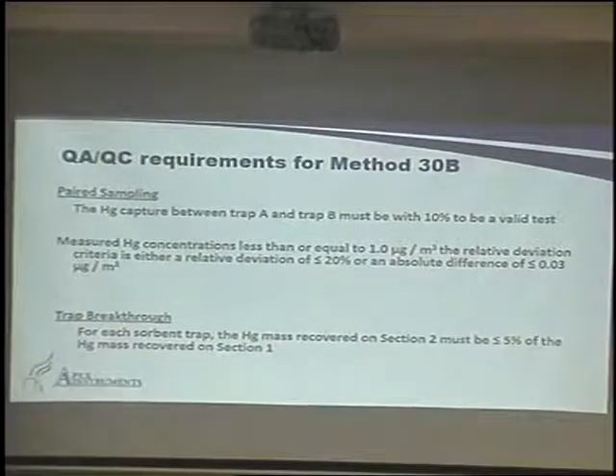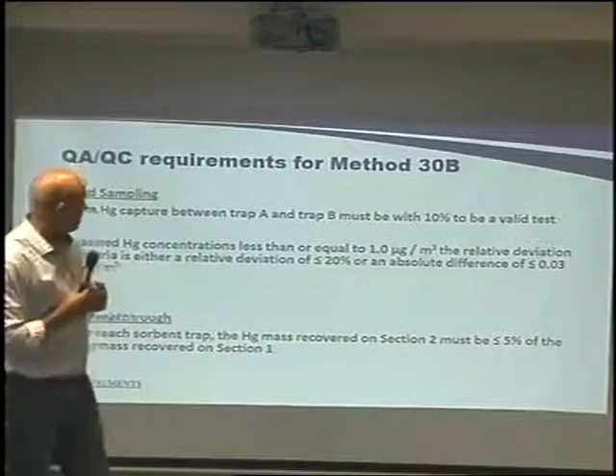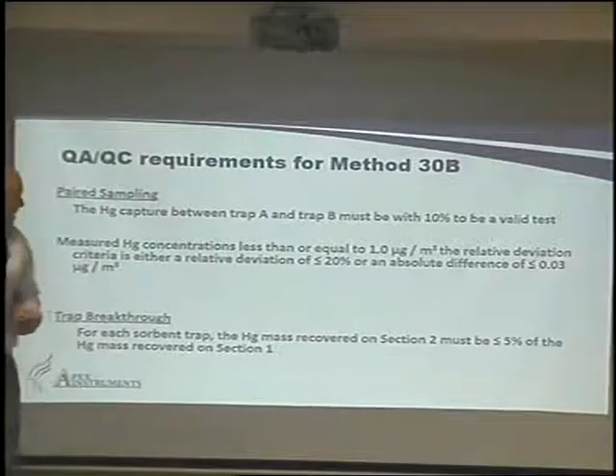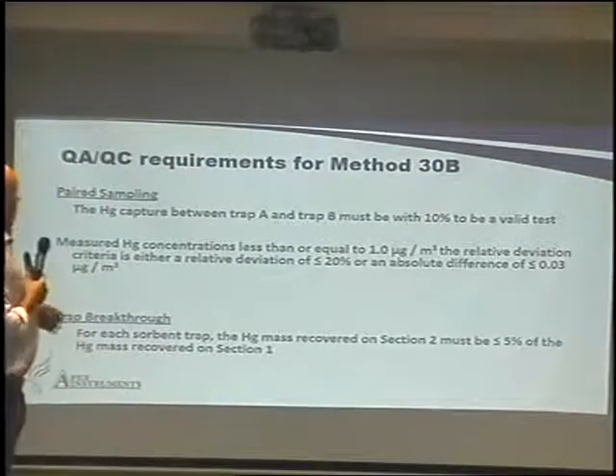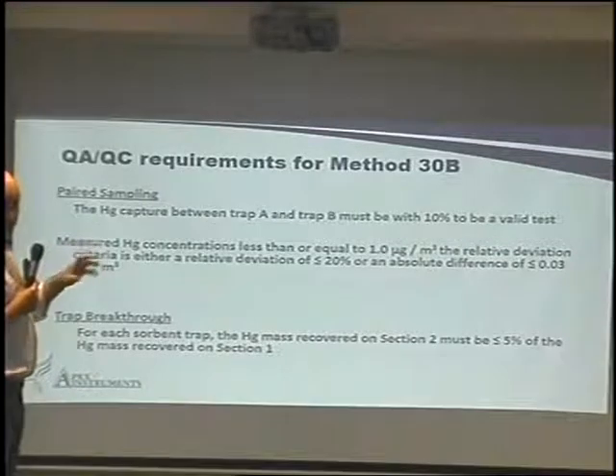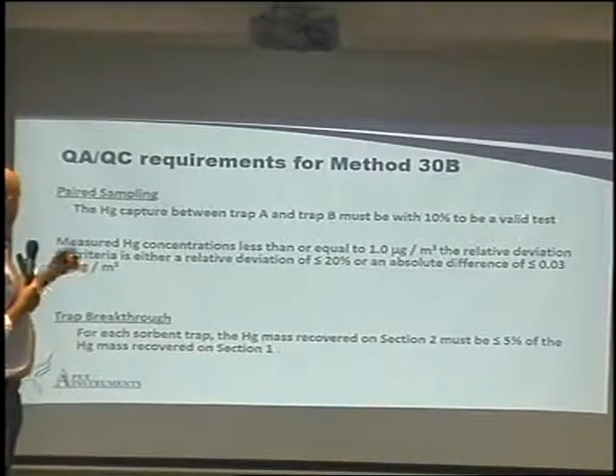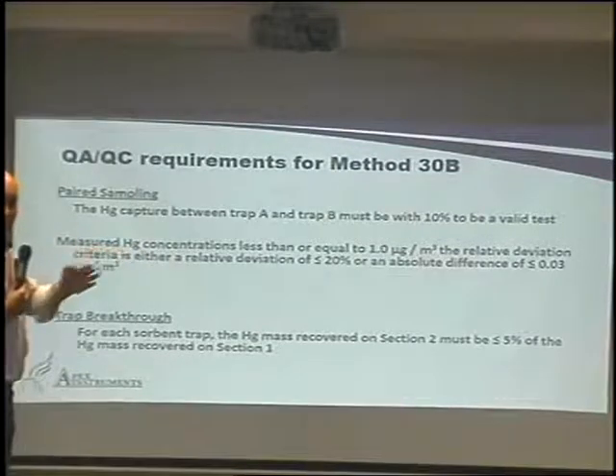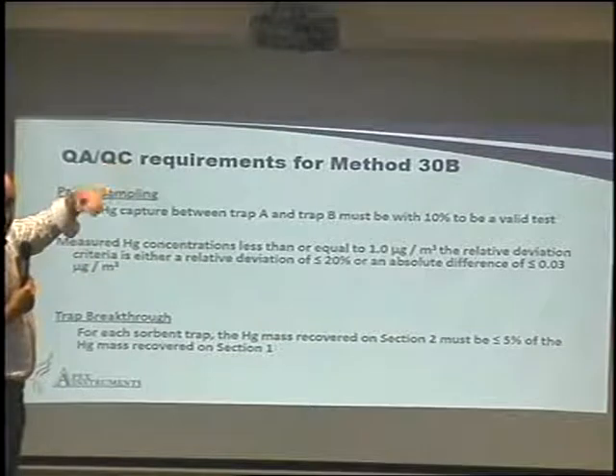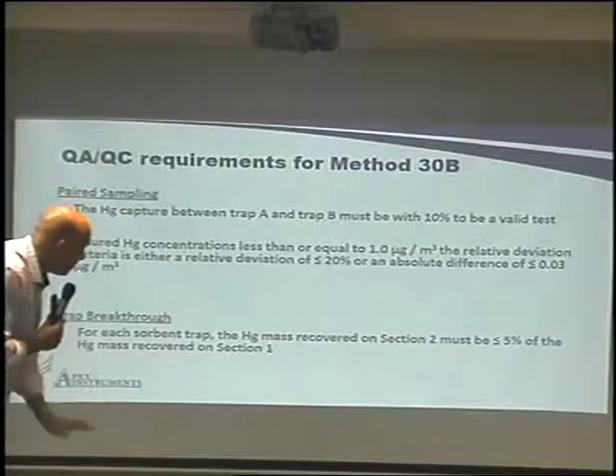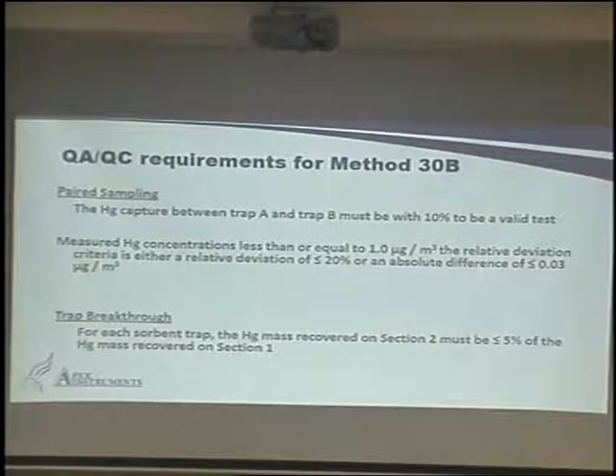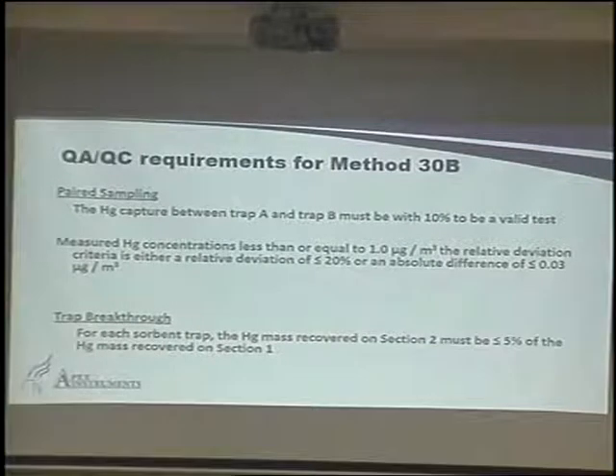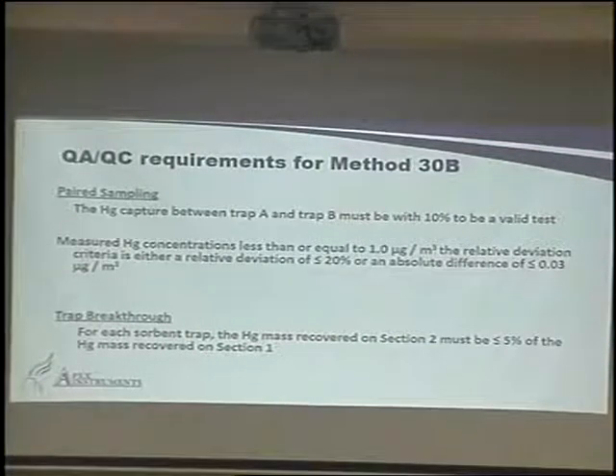The measured mercury concentration, less than or equal to 1 microgram per meter cubed, is the relative deviation criteria, okay, with plus or minus. So it depends on how much mercury you're capturing to how much variation you can have between the traps. At high levels, 10% is fine. If you're sampling really, really low levels, then your window becomes different. It becomes closer. And it's actually based on a value, okay? So again, this is comparing A side, B side, making sure that they're good.